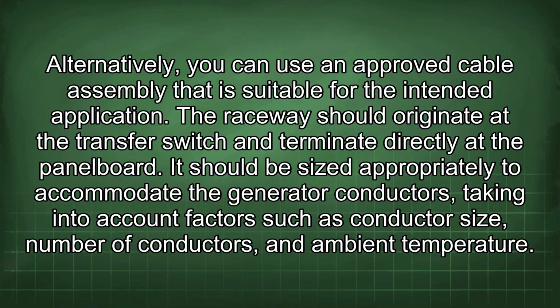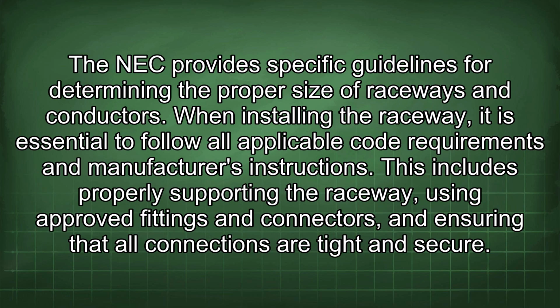It should be sized appropriately to accommodate the generator conductors, taking into account factors such as conductor size, number of conductors, and ambient temperature. The NEC provides specific guidelines for determining the proper size of raceways and conductors. When installing the raceway, it is essential to follow all applicable code requirements and manufacturer's instructions. This includes properly supporting the raceway, using approved fittings and connectors, and ensuring that all connections are tight and secure.